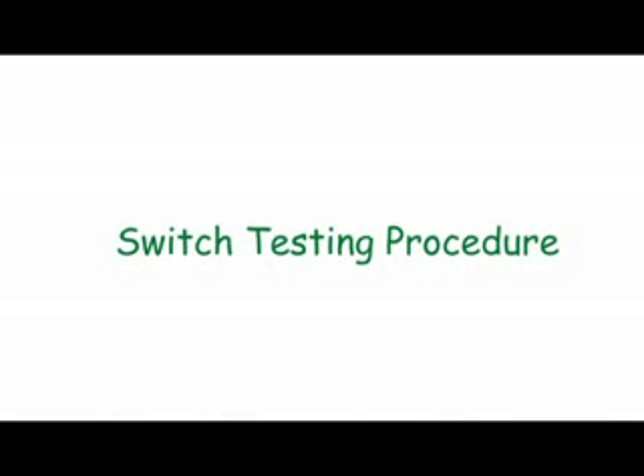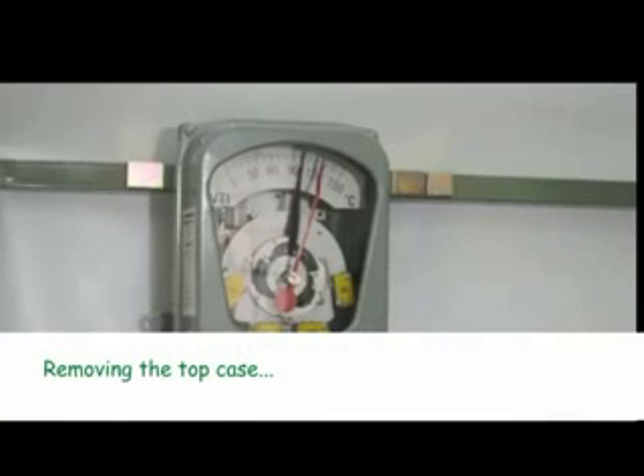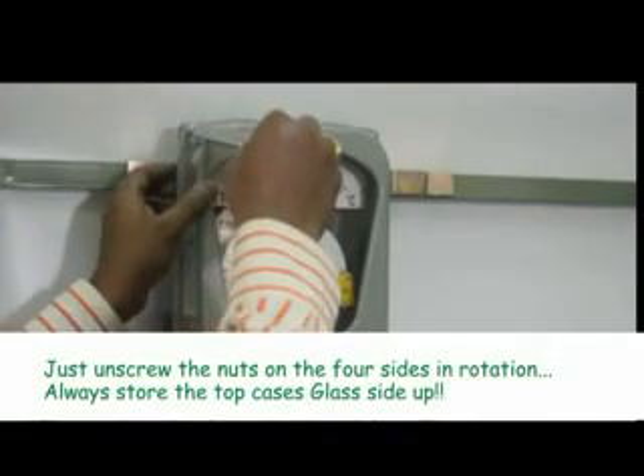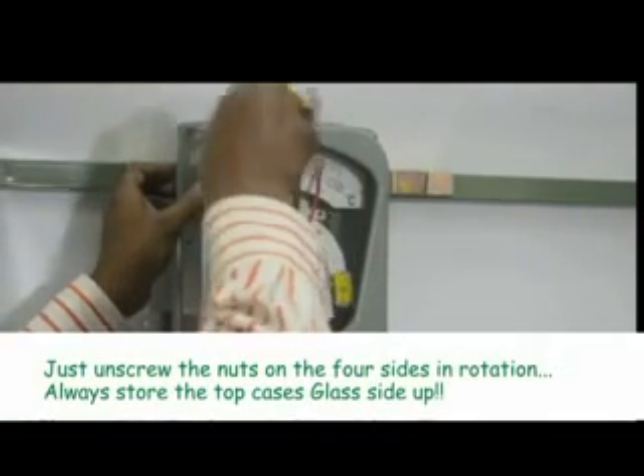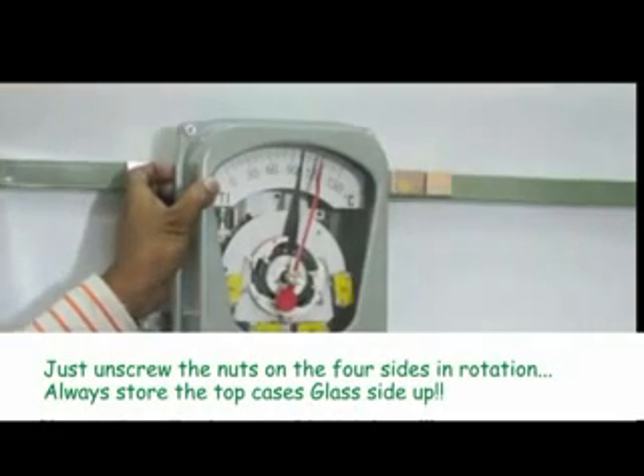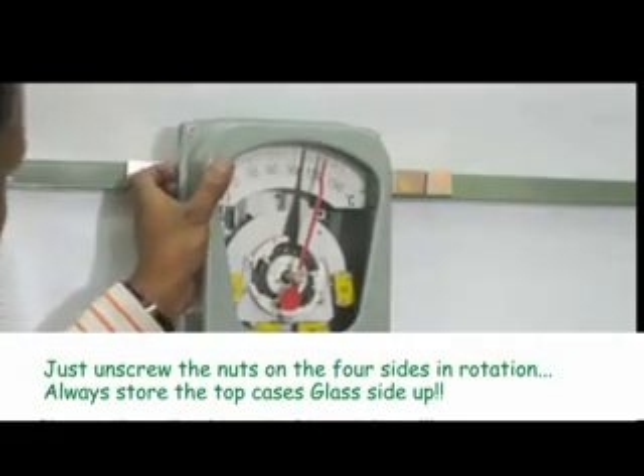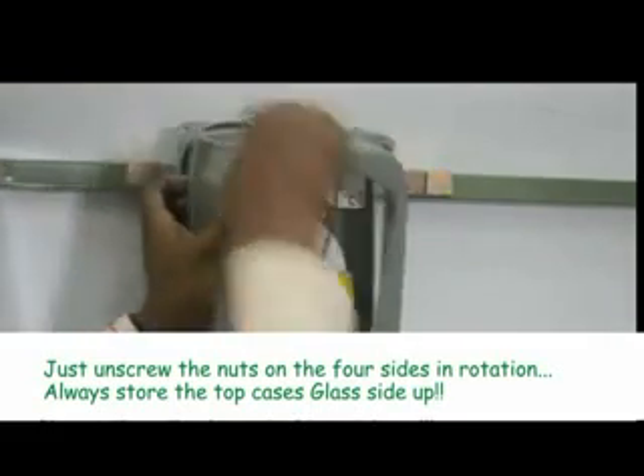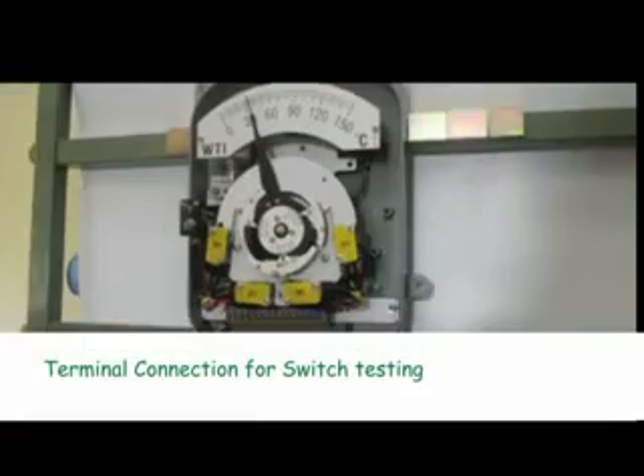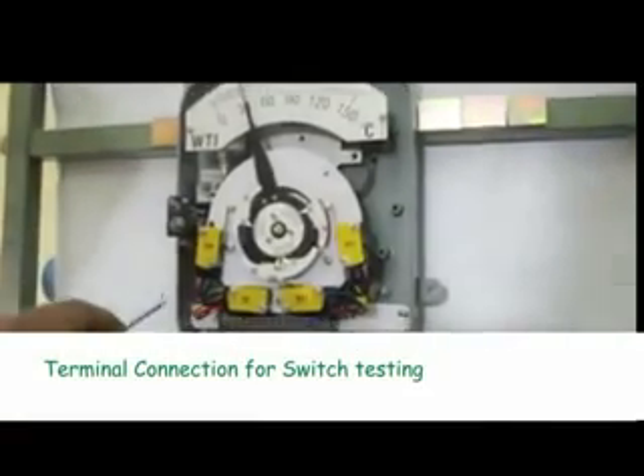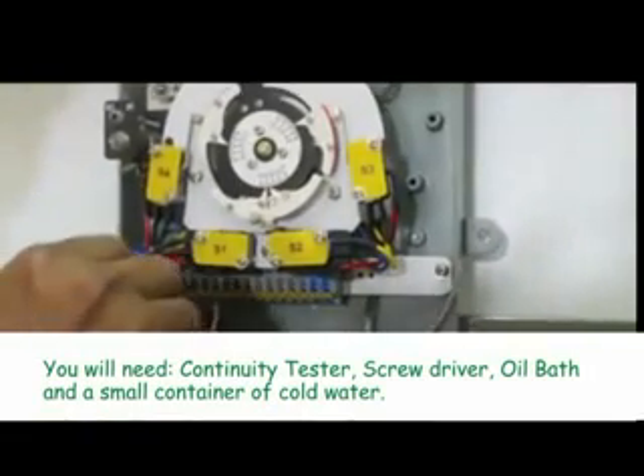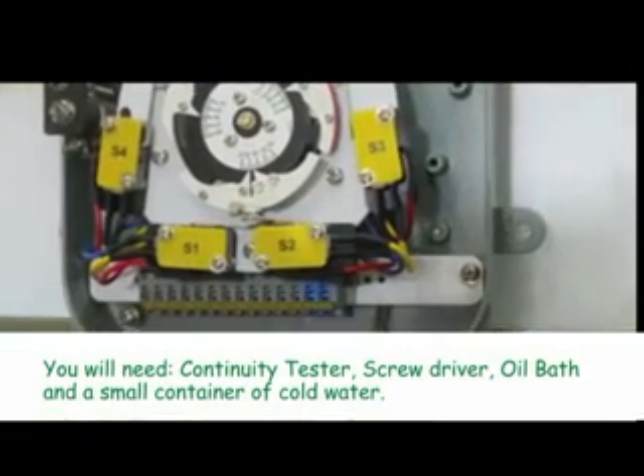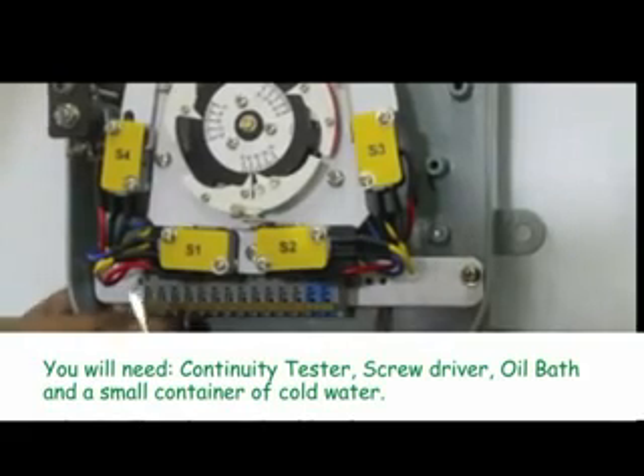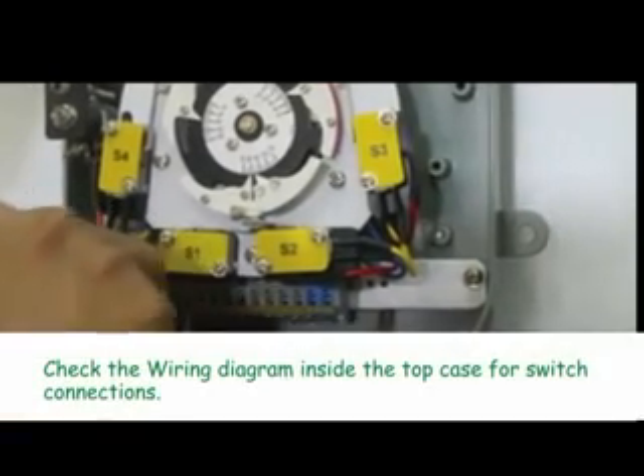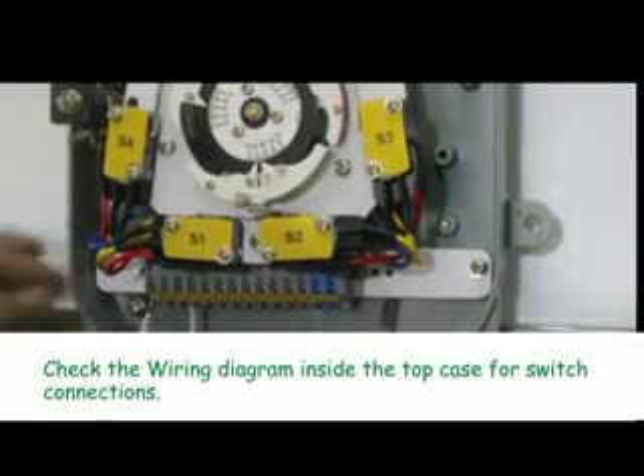Switch testing procedure. Remove the top case. Just unscrew the nuts on the 4 sides in rotation. Always store the top case glass side up. Terminal connection for switch testing. You will need a continuity tester, screwdriver, oil bath and a small container of cold water. Check the wiring diagram inside the top case for switch connections.